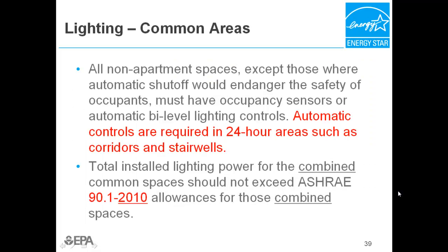Common areas or non-apartment spaces have additional lighting requirements if following the prescriptive path. The prerequisites already require that these common spaces have either occupancy sensors that turn lighting on and off based on motion, or bi-level lighting controls that allow for low-level lighting until triggered, and that provide lighting at full capacity. If following the prescriptive path, these sensors are not required in spaces if automatic shutoff or low-level lighting would endanger the safety of the occupants.